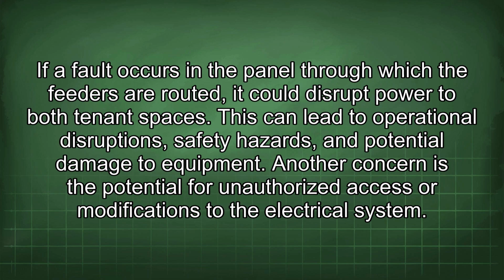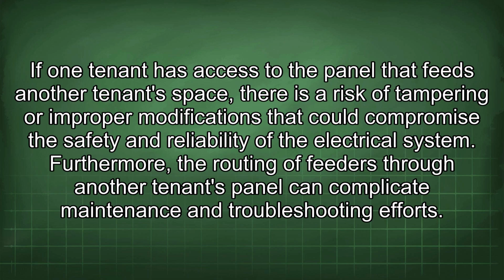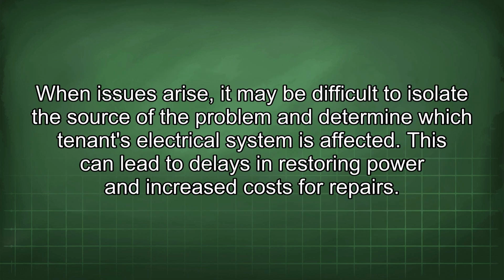Another concern is the potential for unauthorized access or modifications to the electrical system. If one tenant has access to the panel that feeds another tenant space, there is a risk of tampering or improper modifications that could compromise the safety and reliability of the electrical system. Furthermore, the routing of feeders through another tenant's panel can complicate maintenance and troubleshooting efforts. When issues arise, it may be difficult to isolate the source of the problem and determine which tenant's electrical system is affected. This can lead to delays in restoring power and increased costs for repairs.